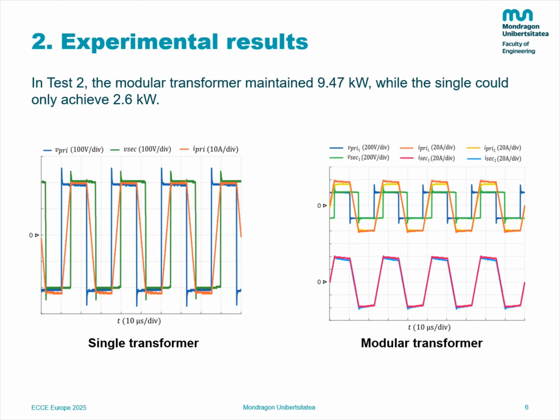In the left, the primary and secondary side AC voltages and the primary side current are shown as previously, and in figure 6, in the right figure, the same parameters are shown, but considering that due to the parallel connection, the AC currents are shared between each module. Compared to test 1, the single transformer is only capable of transferring half current with the same phase shift. However, due to the parallel connection, the modular transformer is capable of maintaining the same current through each module. In this case, the current through each module is equally distributed, without any imbalance as shown in the previous tests with the voltages.